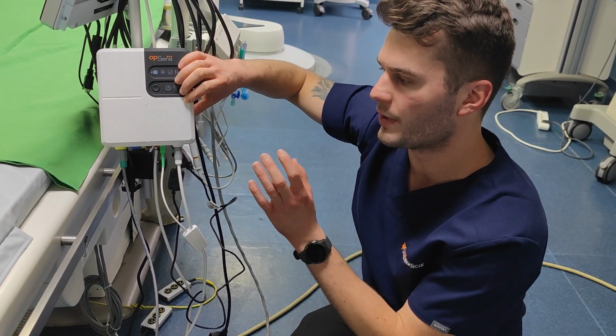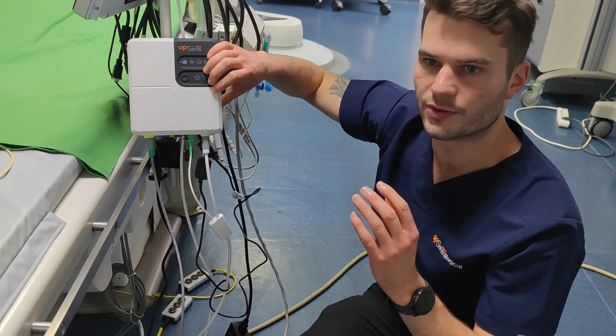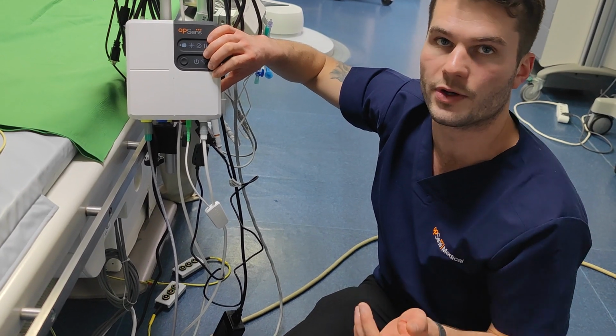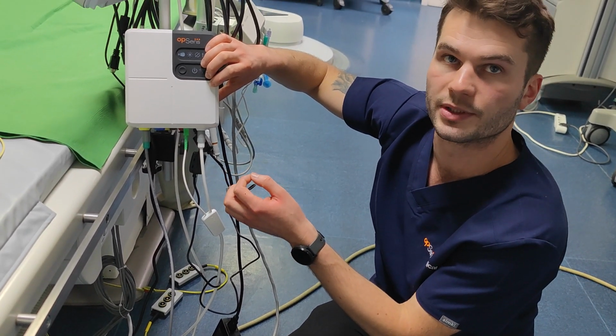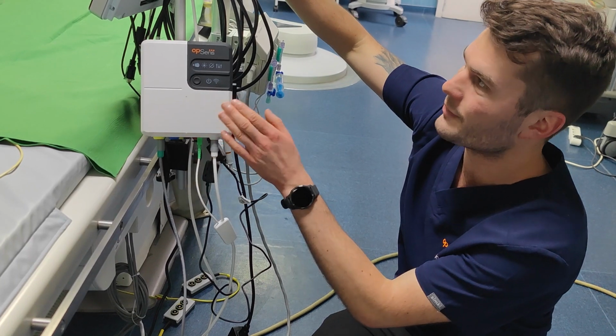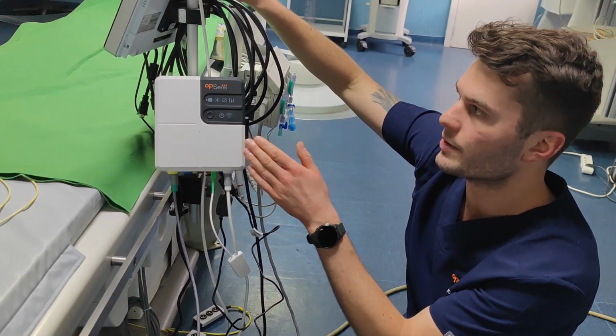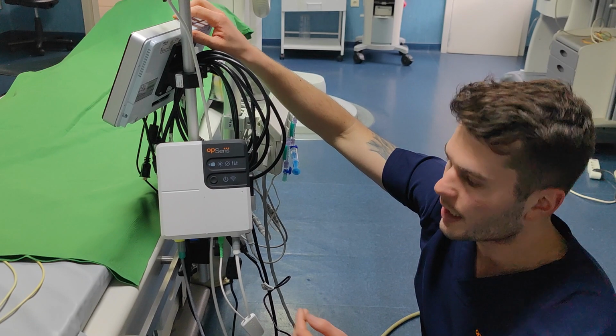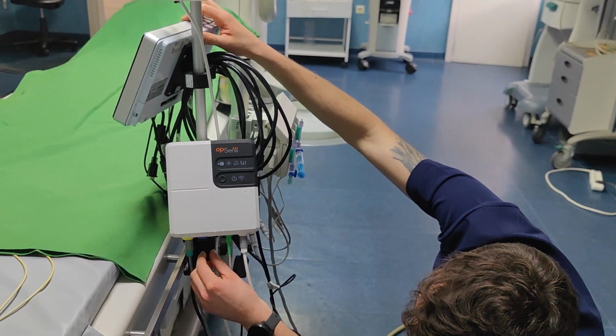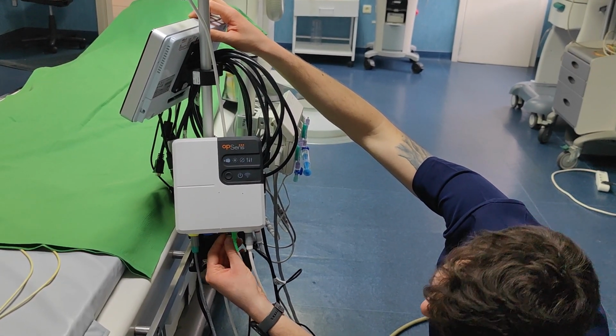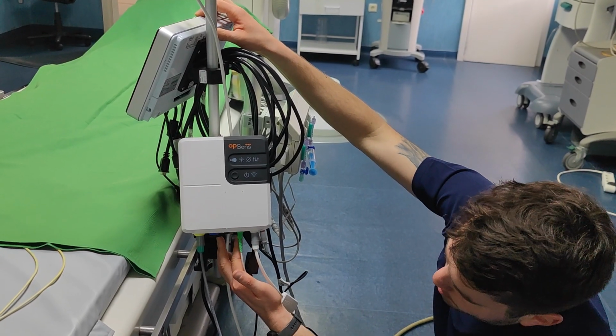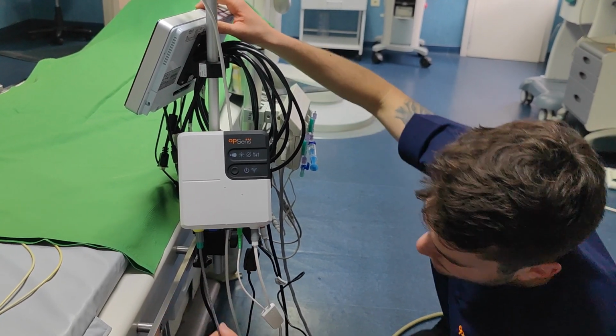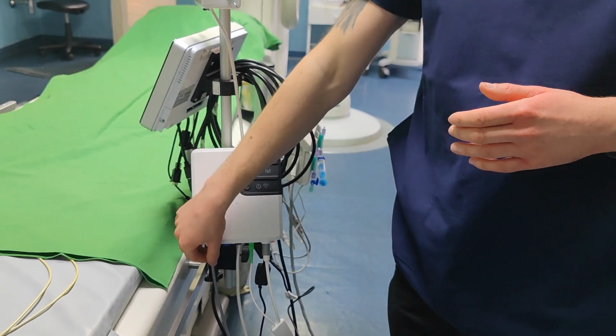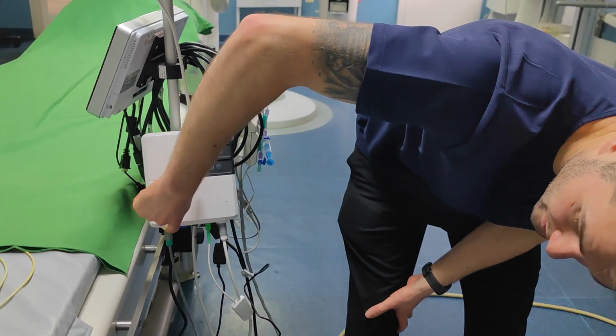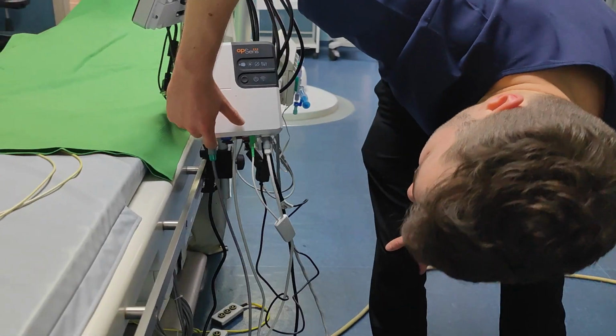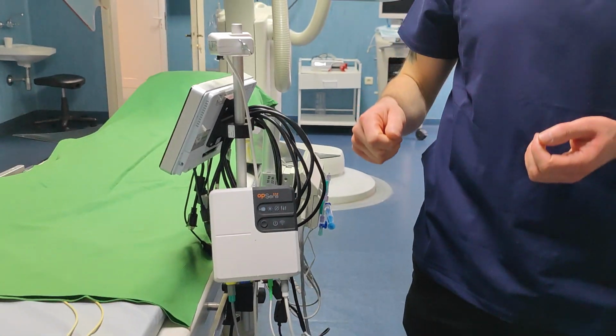So that way you can also use it as an integrated FFR. If they have integrated FFR and they want to use that, you can use that setup. This one, with the analog, everything is on here, so you don't need to feed back to their system. You can with the other. Now with the analog setup, sorry, you do need to calibrate the system, which means the other yellow port, the distal out, needs to be plugged in for that stage.